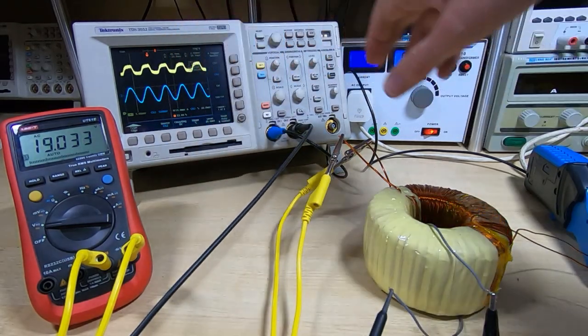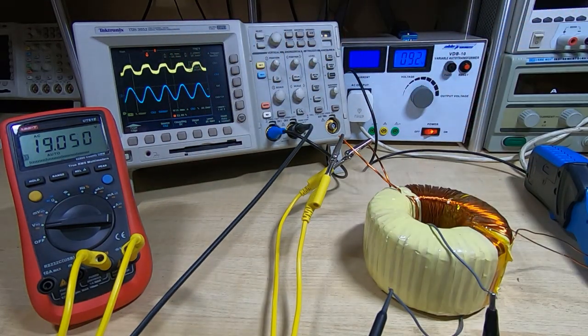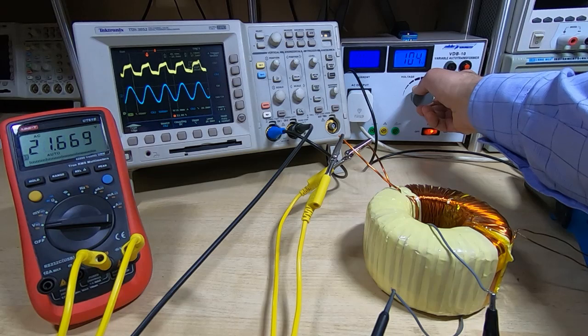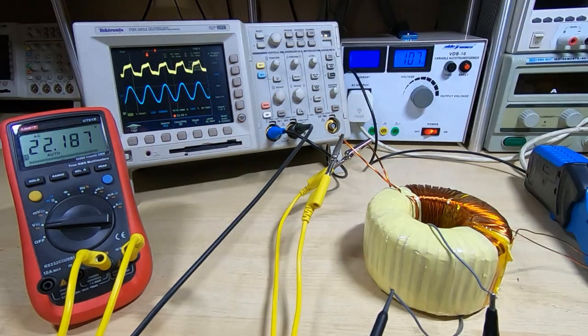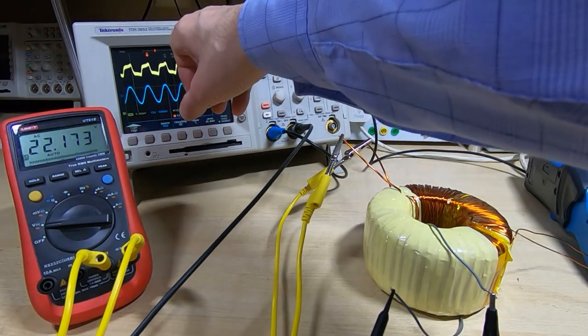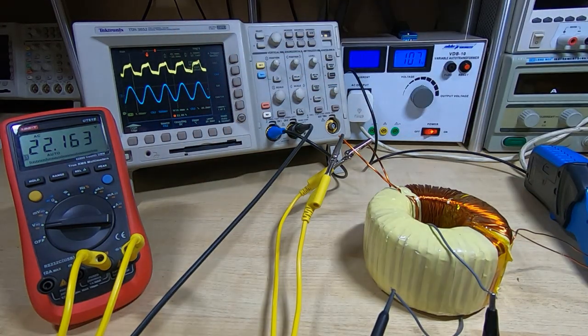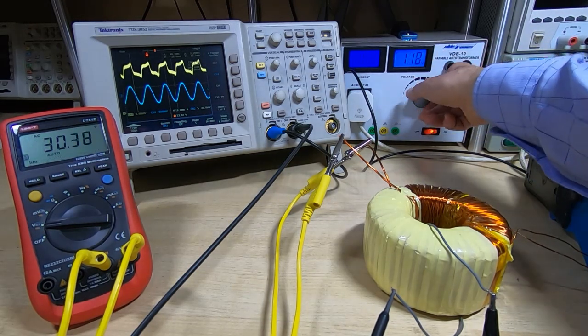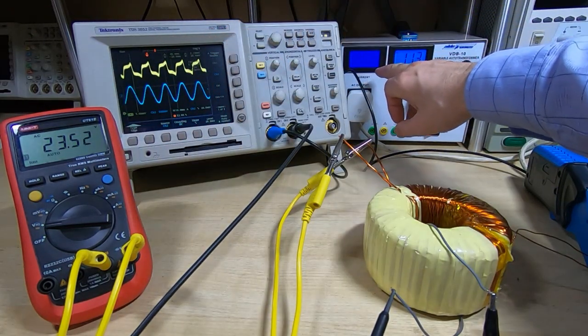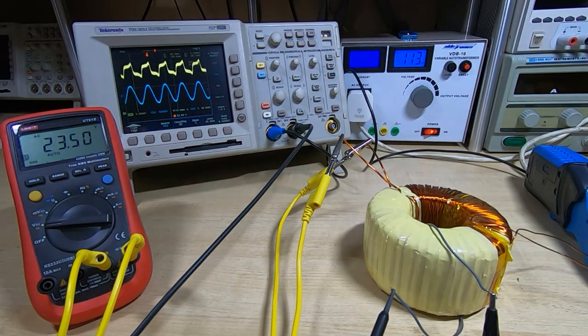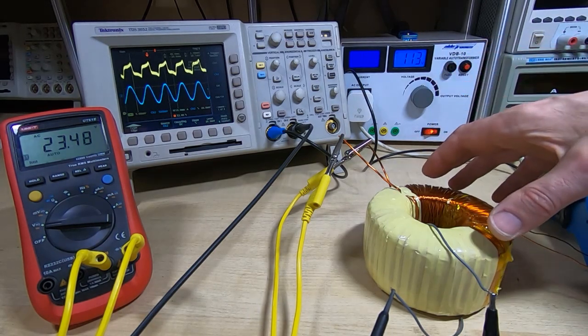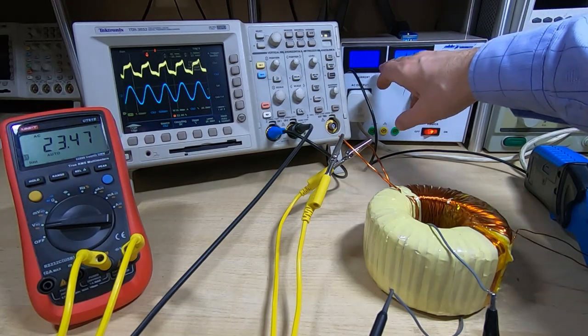I'll carry on increasing the voltage. You can see that the current just continues to square up. The rising edges and falling edges of the current waveform are very steep, and as I said that's to be expected. Currently at 107 volts, we shouldn't be at saturation as yet. The other thing we're looking at here is this is the current, don't forget. If we look at the supply you can see that at the moment we're at about 20 milliamps. Again, that's a good indication that we're not close to saturation. When we get into the saturation zone then the current will start to increase very rapidly.